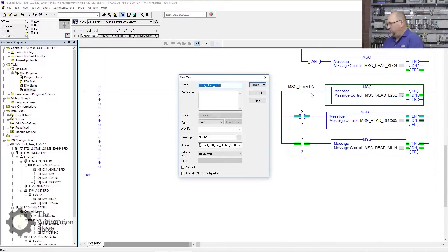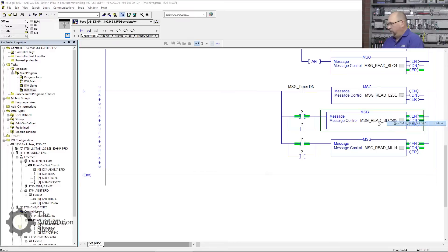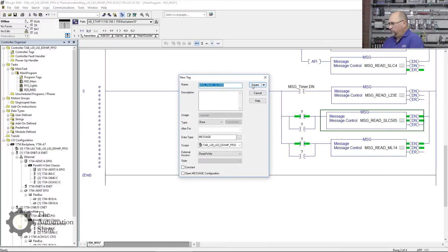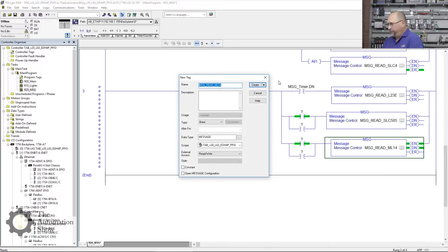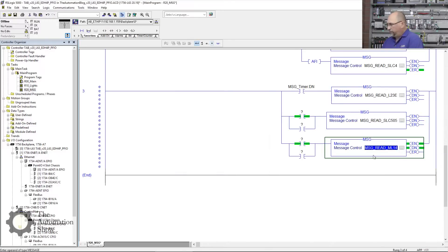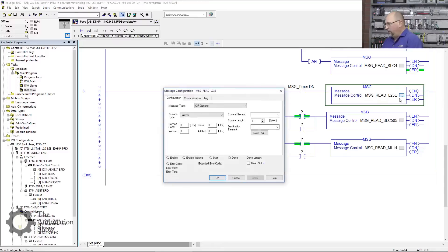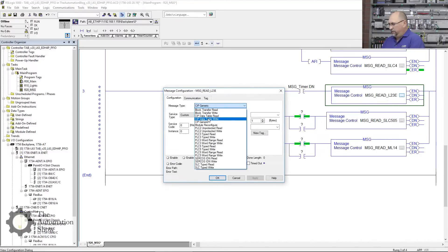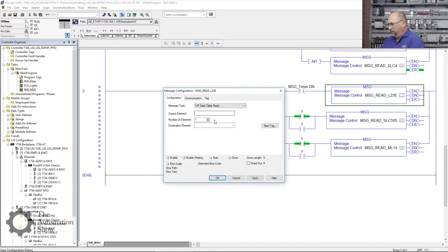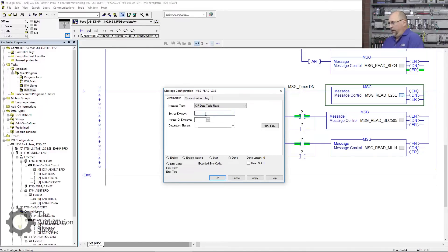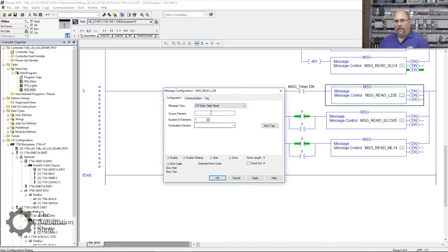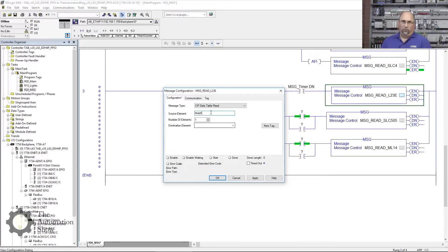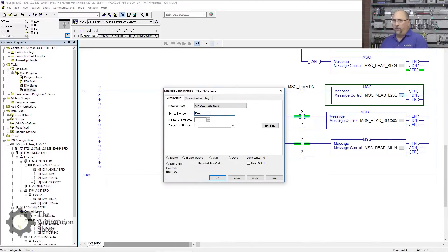Let's go ahead and go into this block. I'm going to do a CIP Data Table Read because we're reading in—this is a data concentrator. The source tag, if you remember when we did the Data Highway Plus, was from Compact Logix. I had a tag called Mold_One, and actually Mold_Two, Mold_Three, Mold_Four, and Mold_Five in those Compact Logix.